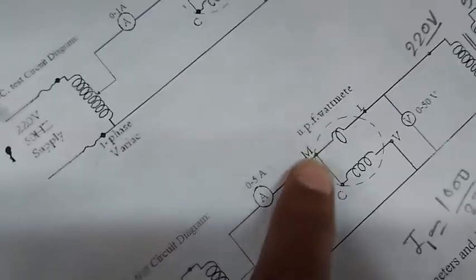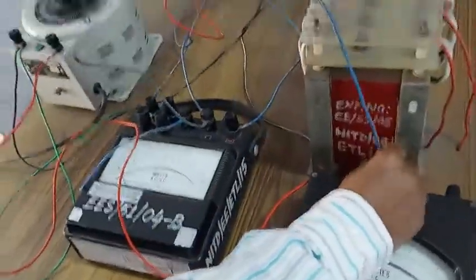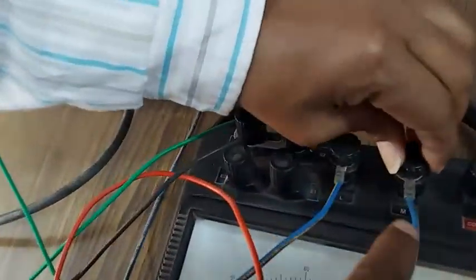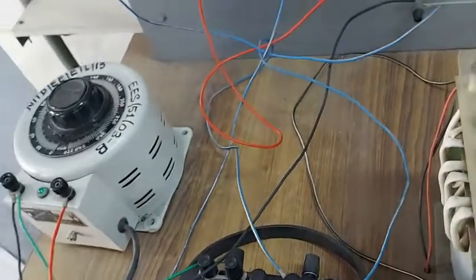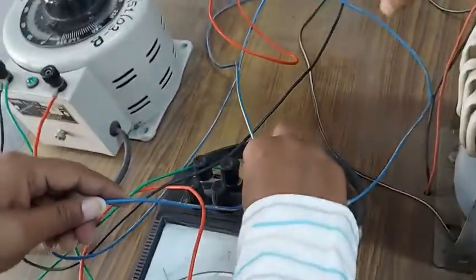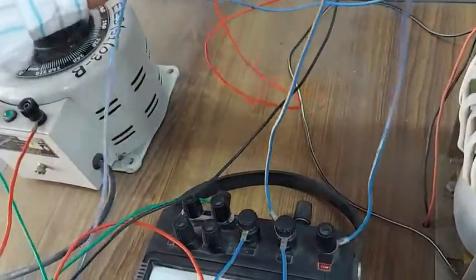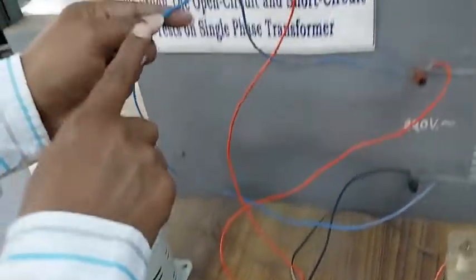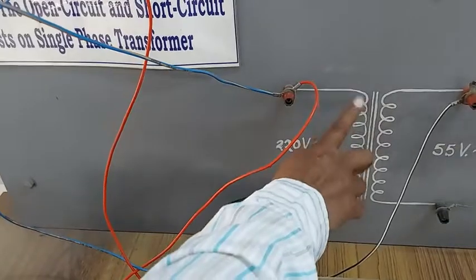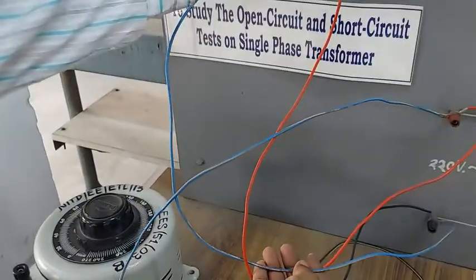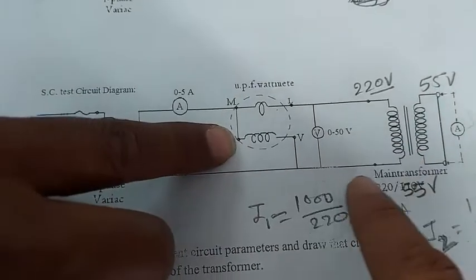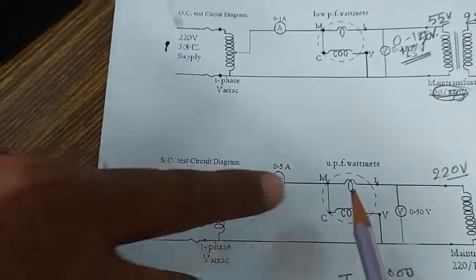Okay, after that ammeter connection, the ammeter is going to the point M, we can see. We will also see the ammeter wire coming, and I will show you clearly. So this is the ammeter wire, and it is going to the point M. This is the point M, and M is the current coil starting point. The ending point is L, and that L will be going to the primary winding or 220 volt side winding, and that end point will go back to the voltmeter point. That is displayed here in the circuit diagram. And a point to be noted is that the M and C points are not connected directly.